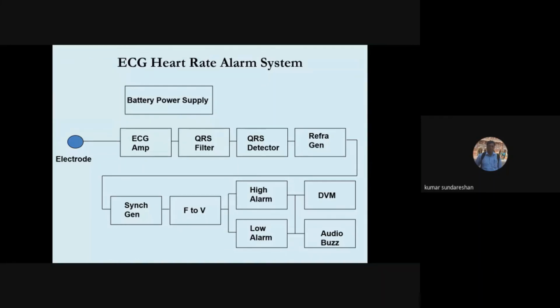So when we talk about the false detection to be avoided, we can use a non-retriggerable monostable multivibrator there, and then we use a universal sync pulse, a 100 millisecond sync pulse, which normally all the ECG equipment manufacturers use. Then you convert the frequency into voltage, and then you are able to set the limits for high alarm or low alarm, like a bradycardia condition or a tachycardia condition. Then you are able to display this heart rate, and you can also have an audio output, a buzzer, which is going to beep the moment the heart rate goes above normal or below normal. So you can set the rates for tachycardia or bradycardia condition.